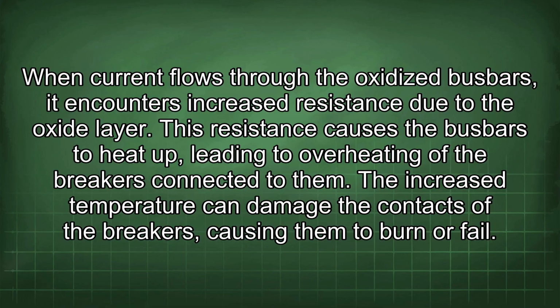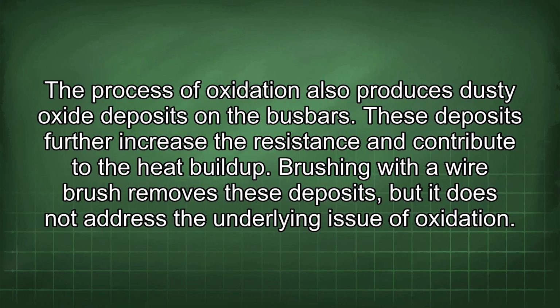The increased temperature can damage the contacts of the breakers, causing them to burn or fail. The process of oxidation also produces dusty oxide deposits on the busbars. These deposits further increase the resistance and contribute to the heat buildup. Brushing with a wire brush removes these deposits, but it does not address the underlying issue of oxidation.